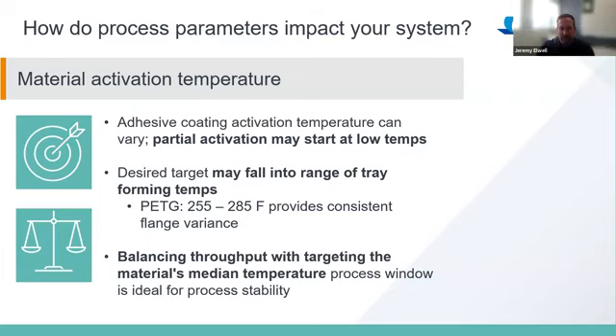So continuing the theme with the lid and adhesives, it's very important to understand your adhesives and when they start to activate. When we're heating up adhesives or the coating on the lid, you're activating all of the ingredients in there, and at lower temperatures, partial activation can happen. So you may see some transfer to the tray material at lower temps, but you may not get a very good adhesive transfer. So it's important to understand during a DOE the low end and the high end: when you're starting to activate, when it's fully activated, when you're getting a good seal, and then at the high end, if you're going too far into over processing. So it's very important to know that.